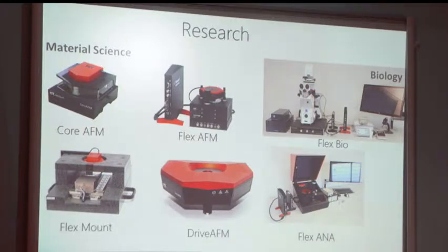And this is our recent development, which is called Drive AFM. Drive AFM is more or less fully automated. You are not going to adjust anything by using any screw or anything. You just connect the wires and you control everything via software. The laser alignment, the sample movement, the detector alignment, everything is fully automated using Drive AFM. So I'm going to talk a little bit more about Drive AFM.